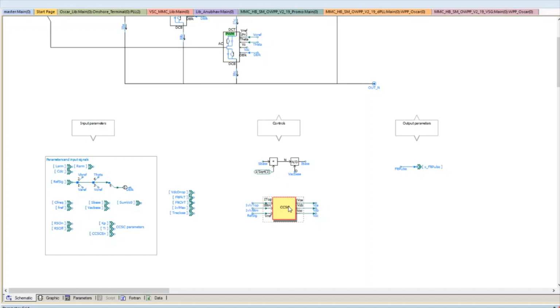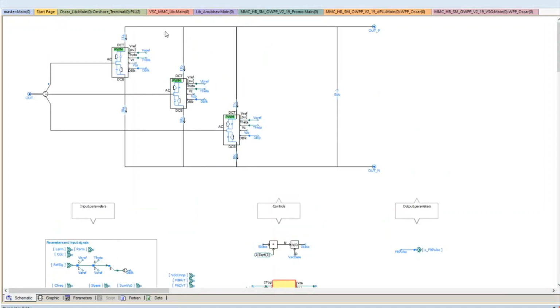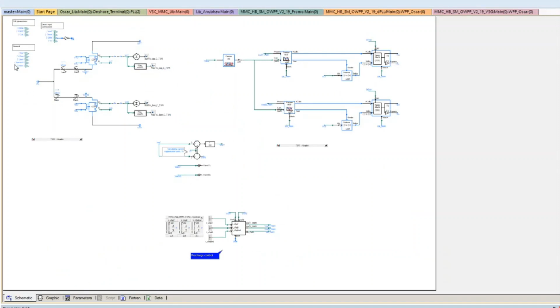And there is circulating current suppression control present, which is to eliminate currents that flow between the submodules due to an imbalance in the capacitor cell voltages. And inside the submodules, you have the PWM generation and sorting algorithms, the inner controls of the MMC.